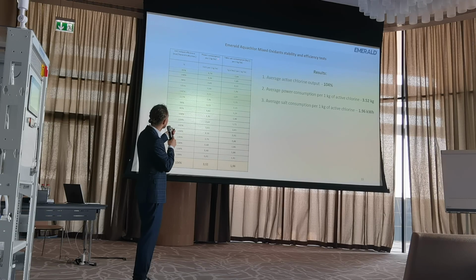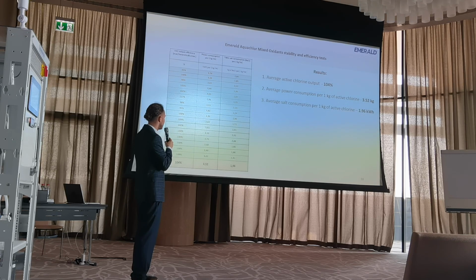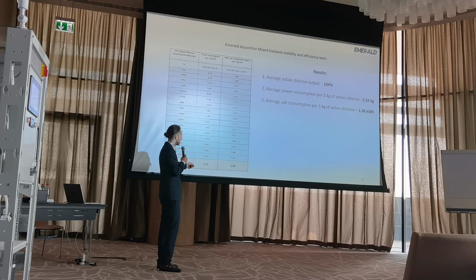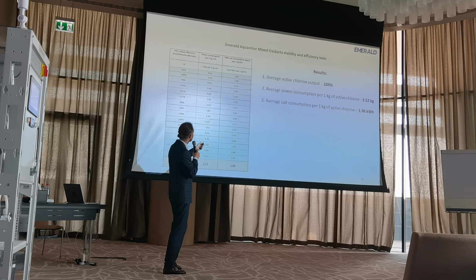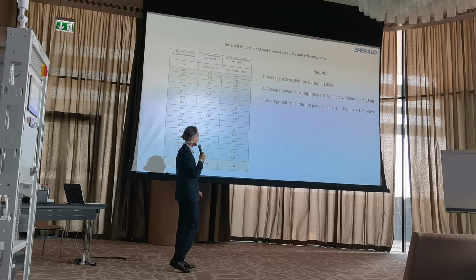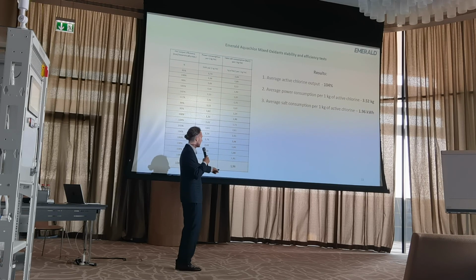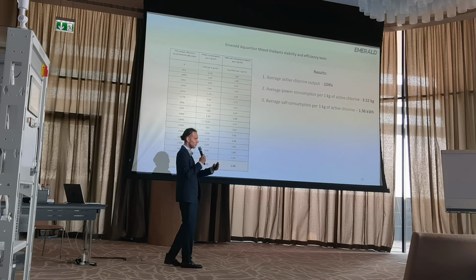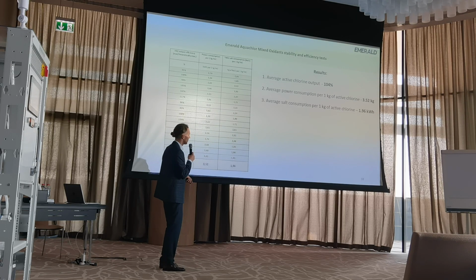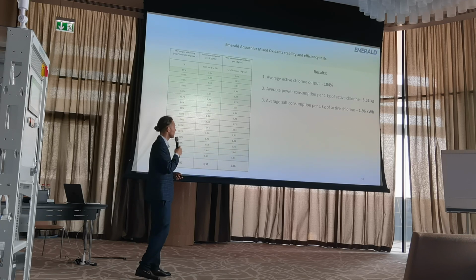Second, this is power consumption per 1 kg. So they measured the real power consumption of the machine, and taking the amount of chlorine which is produced, we get a figure even better than we claimed in the presentation. So it is 3.52 kilowatt-hours per 1 kg of active chlorine. Traditional sodium hypochlorite generators will have 6-7 kilowatt-hours, something like this. And the salt consumption, we got 1.96. Traditional sodium hypochlorite generators have 3 kg per kg. So we have 2 kg of salt for 1 kg of chlorine. Traditional systems consume 3 kg of salt per 1 kg of chlorine.